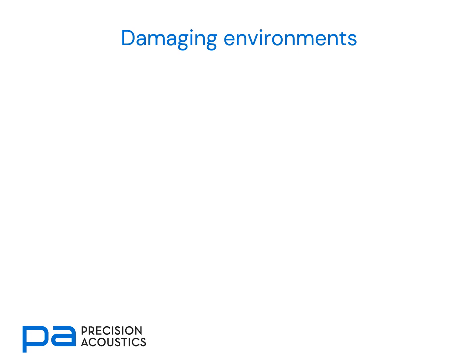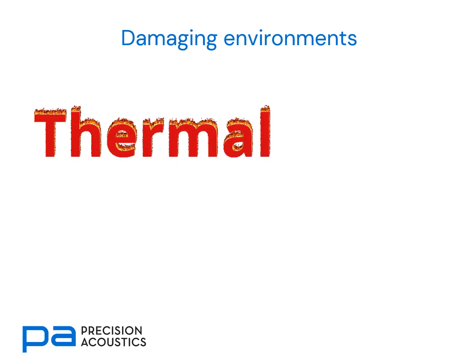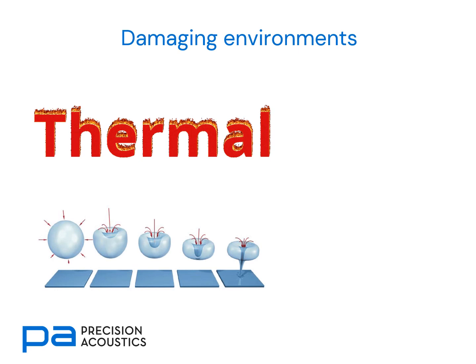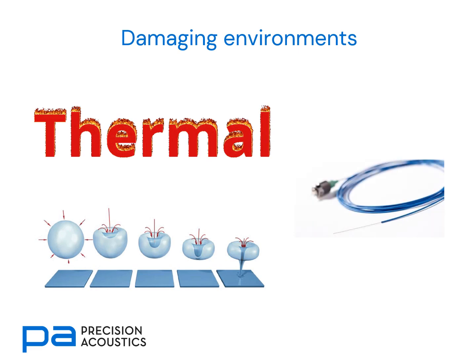The environment in which we're making measurements is also important. With many therapeutic fields, there's a risk of thermal damage and of mechanical cavitation damage, and an expensive sensor placed within those fields could very easily become destroyed. This is one of the other advantages of optical fibre hydrophones, where the sensors themselves are relatively cheap and can be replaced if they become damaged under these extreme conditions.